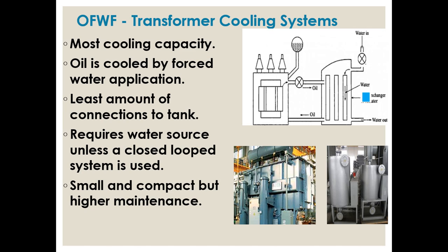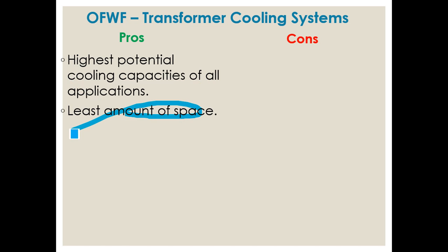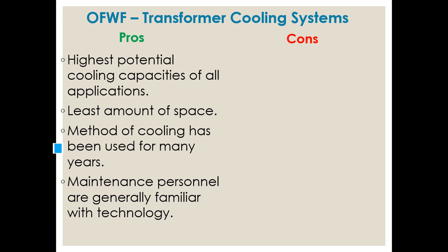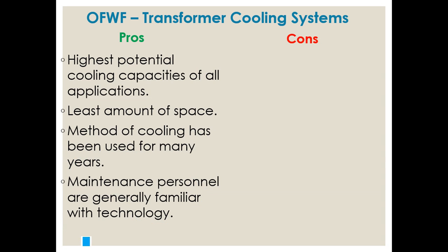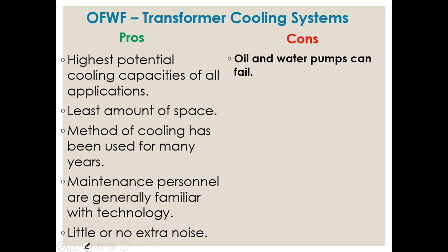OFWF provides the highest cooling capacity among all applications. High capacity machines use OFWF where space is a constraint, as the size is reduced with this cooling method. This method has been in use for many years and is proven technology. Maintenance personnel are already familiar with this technology. Noise levels are lower because cooling is done through water flow rather than fans.